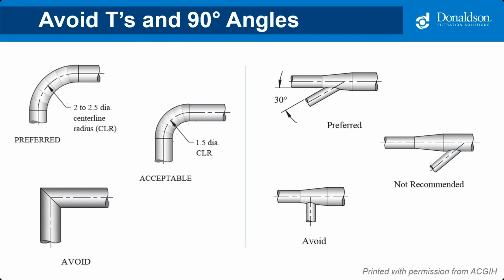Elbows, pictured on the left, should be 2 to 2.5 diameter centerline radius, except where space does not permit, in which case a 1.5 diameter centerline radius is acceptable. But if the elbows are mitered 90 degrees in turns, all the air must slow down, turn, and then speed back up. This creates a ton of turbulence, which adds more energy consumption and higher static pressure. Same thing for branch entries, pictured on the right, and you can see that a 30-degree angle is preferred.